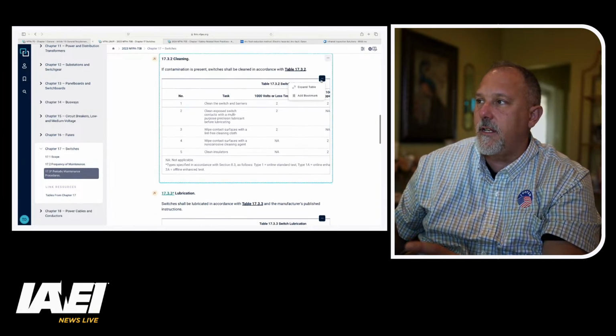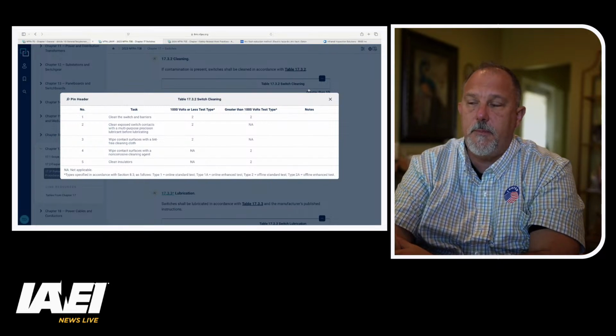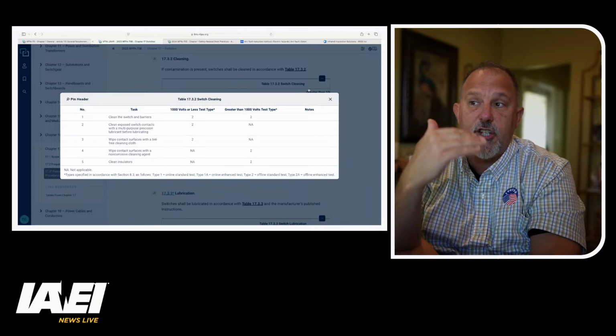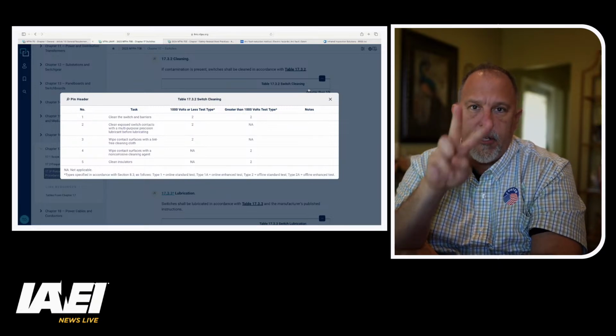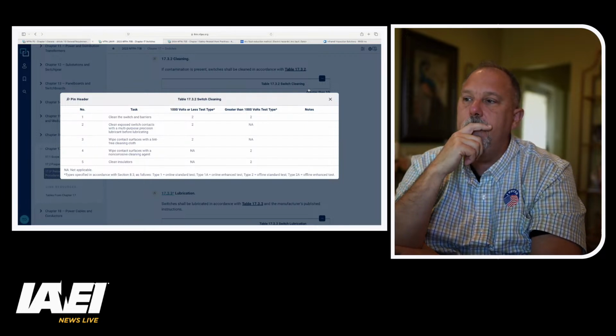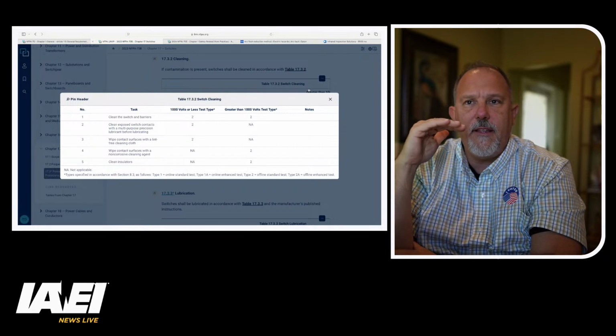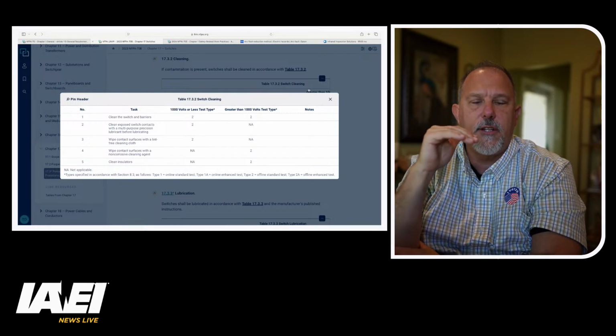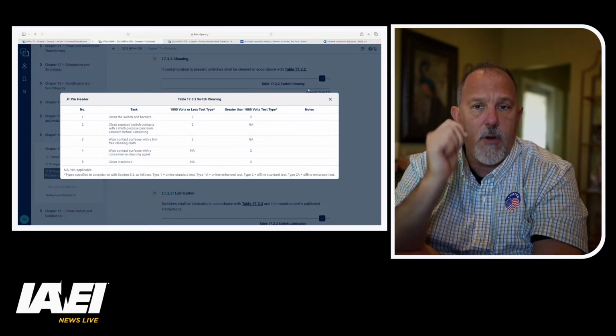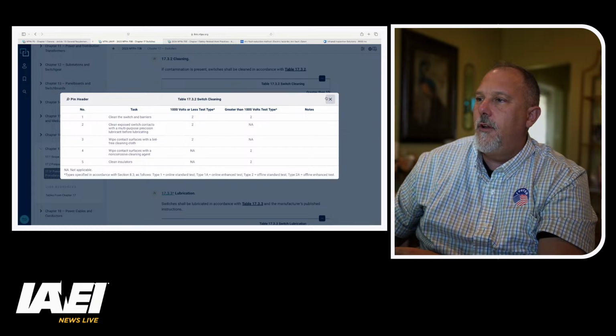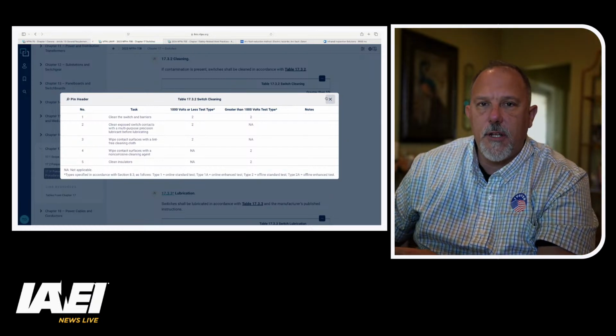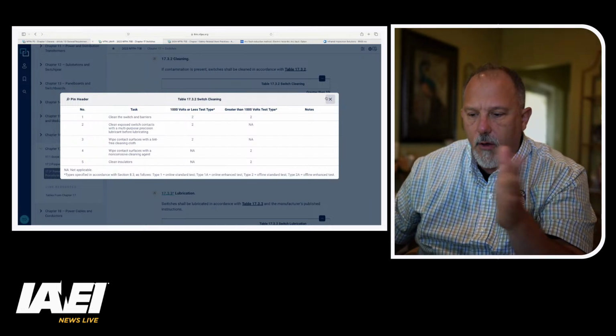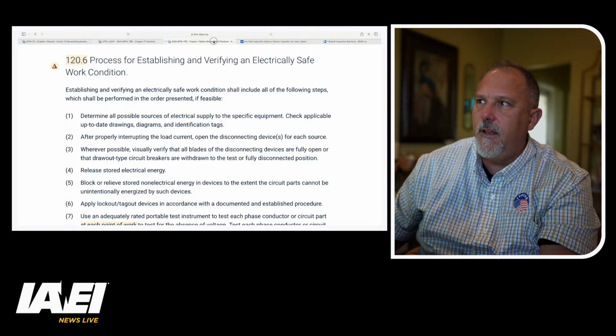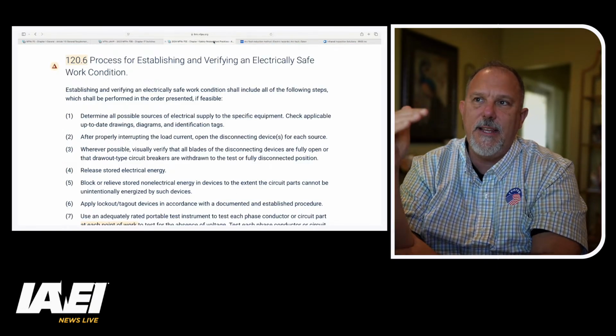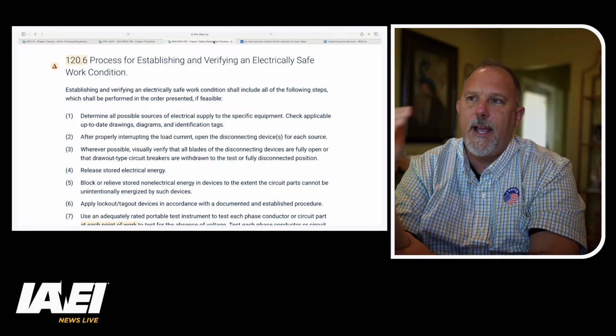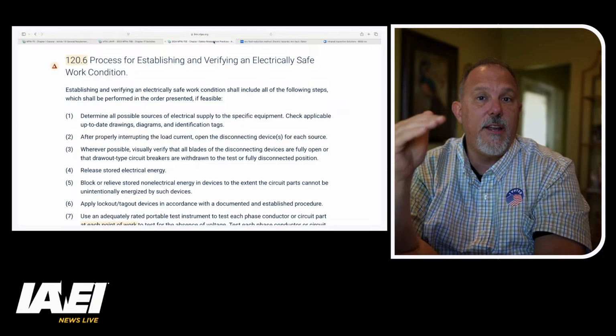Let's just take a look at cleaning. It tells me that I have to clean, so I'm in 70B now, and I have to clean the switch and barriers. I have to clean exposed contacts, and all of those are a 2, and a 2 means it's in an electrically safe work condition. So if on a non-fused disconnect switch the only action that I have to perform energized is thermography, and I can establish an electrically safe work condition in all of these other cases, is the act of establishing, now I'm in 70E, is the act of establishing and verifying an electrically safe work condition considered energized work?